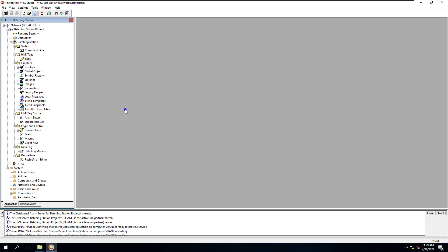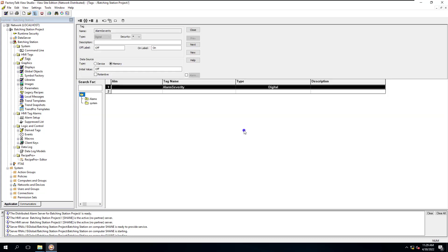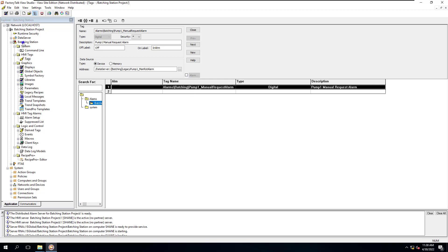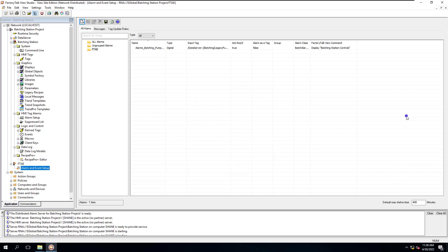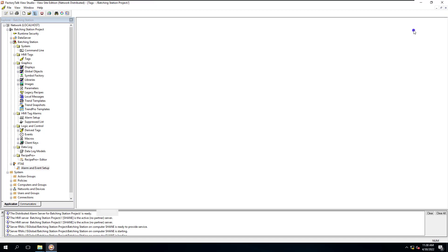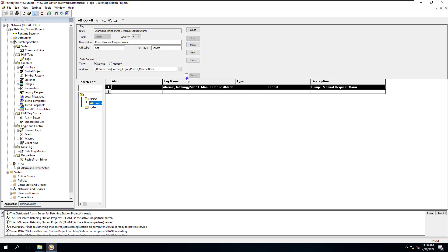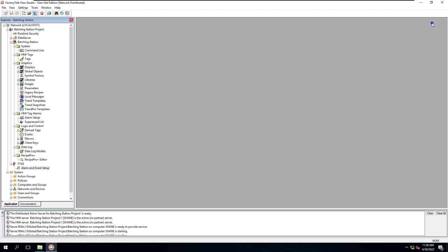The key takeaway: after you build your FTAE alarms and want to test on a live system, just uncheck the box on your legacy HMI tag alarms and hit Accept. Your tags will no longer work on the old legacy system, but they will work on your alarms and events summary. You will need to replace the legacy alarm screen with the new alarms and events summary screen — just keep that in mind.